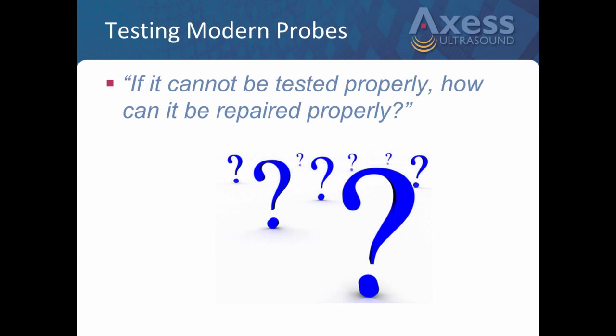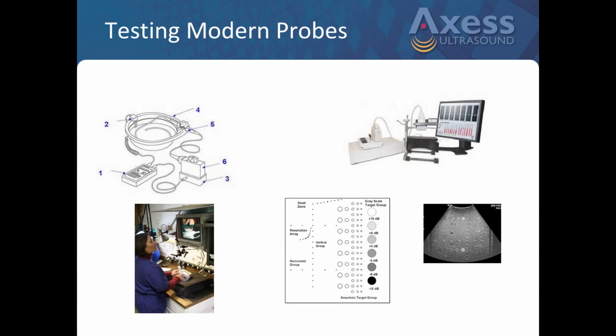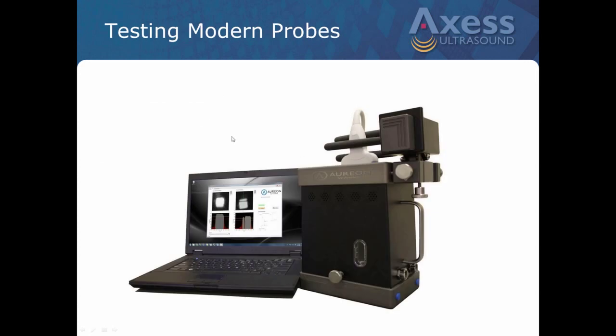The question about the cable, I can probably answer that for you right now. Using this device is one way, again the best way in my humble opinion, to identify whether it's the cable or the element. What we can tell by this, just to share that with Chandra, is that a dead element is going to look one way on this test. We can see if there's a bad cable; the reading we get is going to look different. We can see that the cable is open, broken, etc., but yet the array is still performing. We still have a beam profile on the array. So that's how we can tell with that.